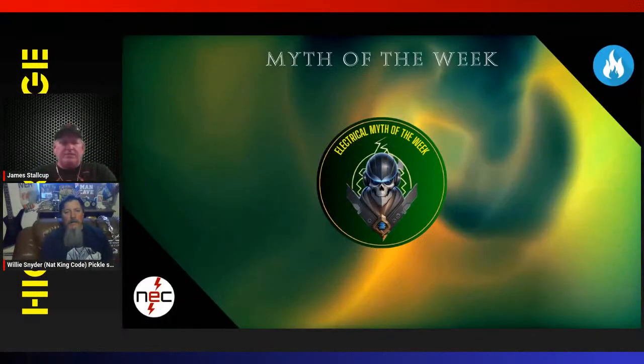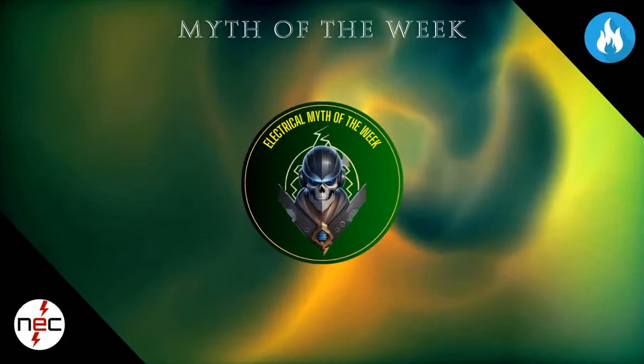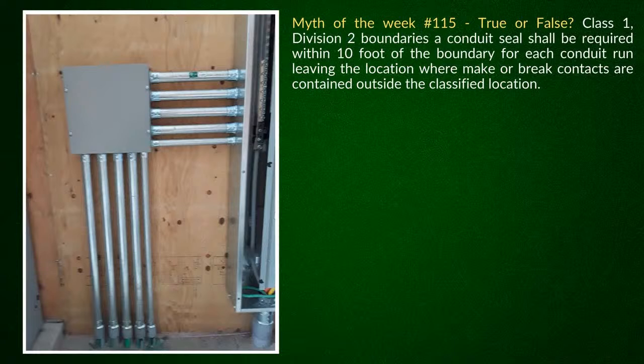All right, we had an awesome myth this week. I'm digging deep into the myth bank, Myth of the Week number 115. True or false: Class 1, Div 2 boundaries. A conduit seal shall be required within 10 feet of the boundary for each conduit run leaving the location, where make or break contacts are outside the classified location, but that's irrelevant.